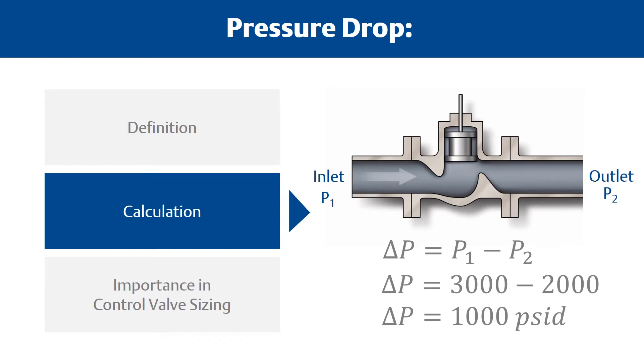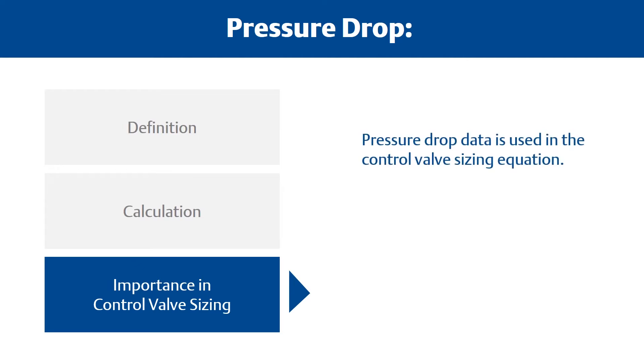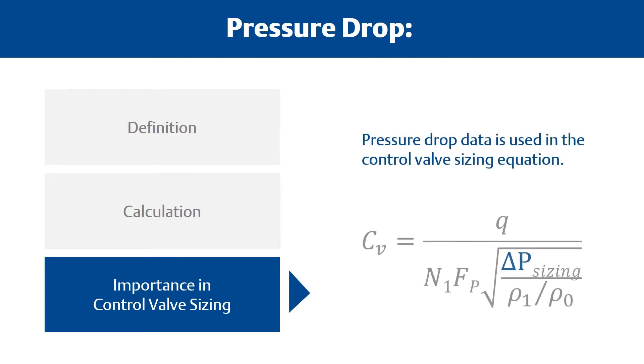If the flow rate is going to vary, repeat the calculation of P1 and P2 at each flow rate. Pressure drop data is used in the control valve sizing equation and is critical for proper valve selection.